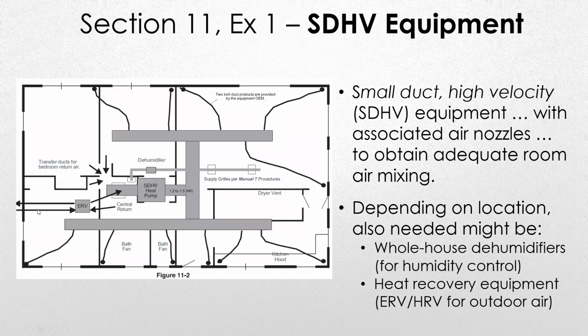you can see that an ERV was added in here to handle the outdoor air load, because it's typically so humid. So basically, an ERV would help us deal with the disparity in the ratio of sensible to latent.